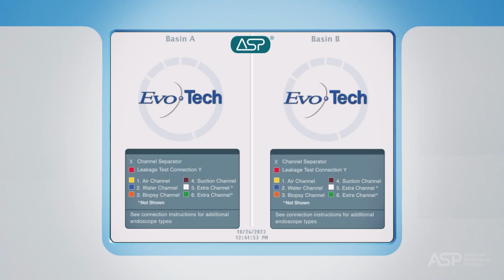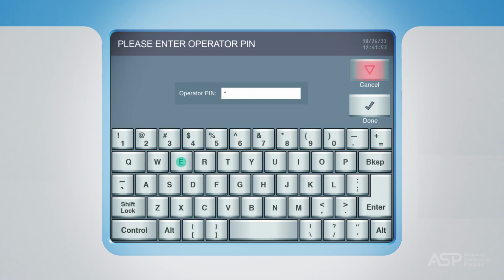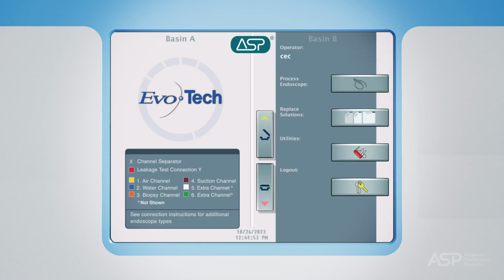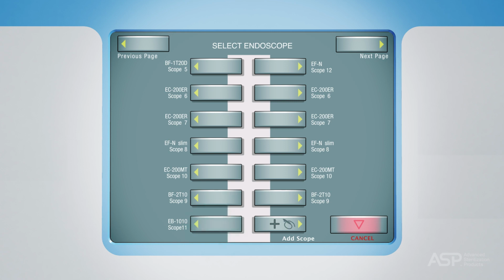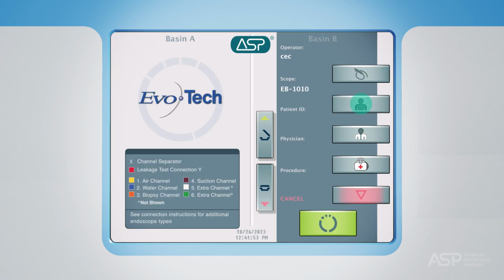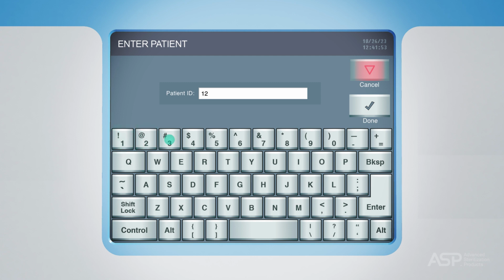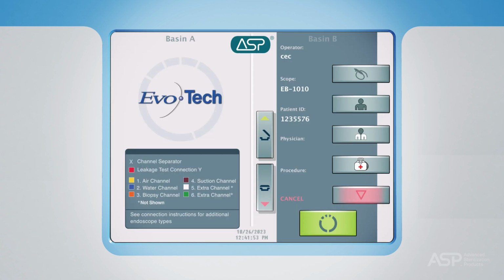To start a cycle, touch the side of the startup control panel in which your scope has been placed, basin A or B. If your facility has opted to require operator identification, you will enter your user PIN. Select the endoscope ID from the drop-down scope list. Select Patient ID and enter the patient information, if applicable, for your department. A scanner can be connected to the EVOTECH ECR to automate patient data input. Next, select the physician and the type of procedure, if applicable. Then touch the green Start button to begin the cycle.